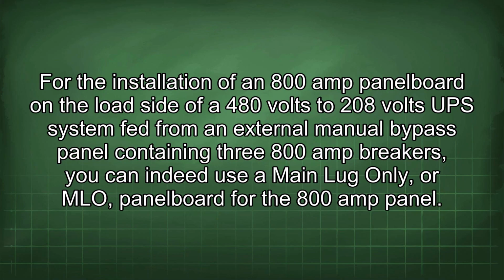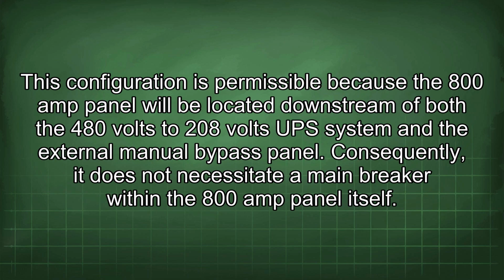For the installation of an 800 amp panel board on the load side of a 480 volts to 208 volts UPS system fed from an external manual bypass panel containing 3 800 amp breakers, you can indeed use a main lug only, or MLO, panel board for the 800 amp panel. This configuration is permissible because the 800 amp panel will be located downstream of both the 480 volts to 208 volts UPS system and the external manual bypass panel. Consequently, it does not necessitate a main breaker within the 800 amp panel itself.